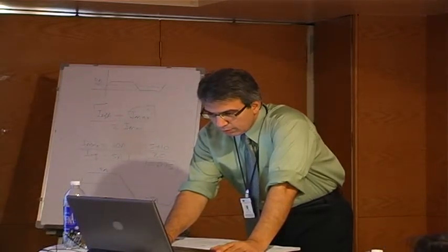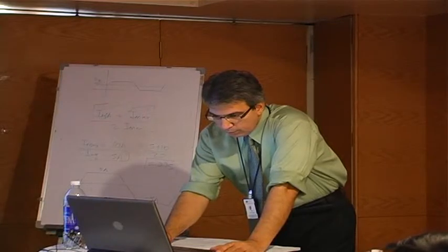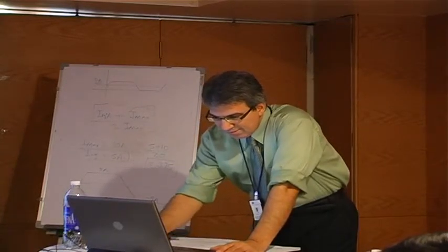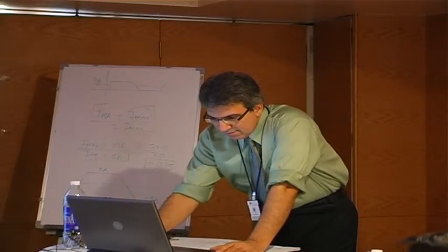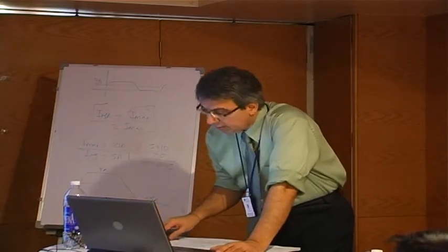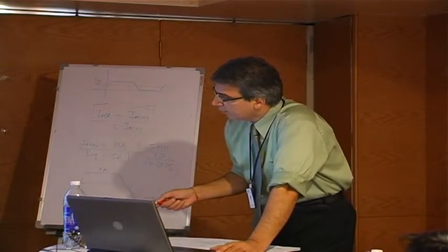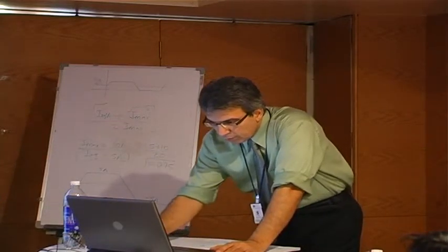This is the power output, and here are the harmonics of the phase A current. So this harmonic here is really the rotational frequency harmonic, and then you have got these harmonics. It's a multiple of the rotational frequency. Let's see if I can blow it up.